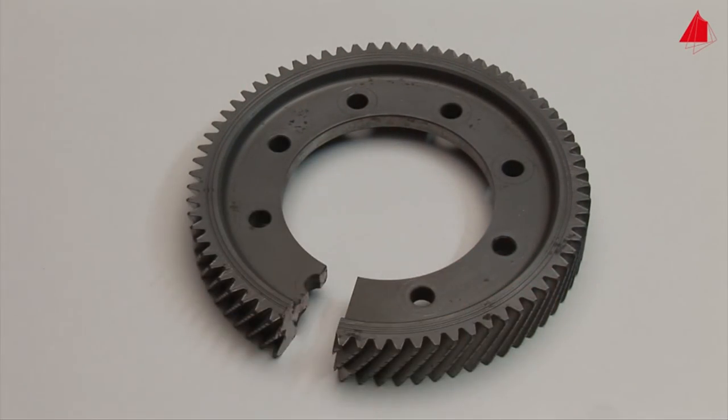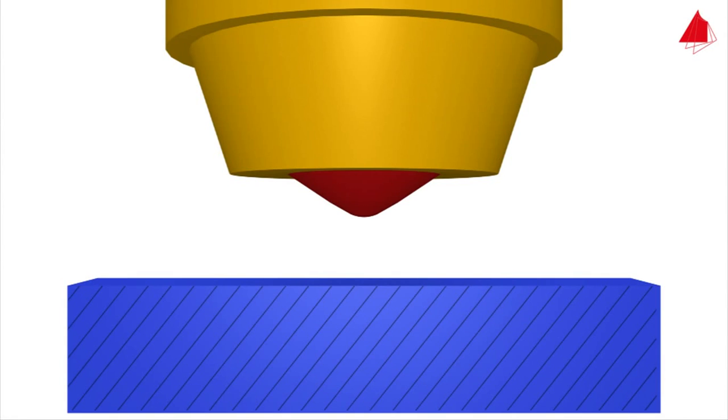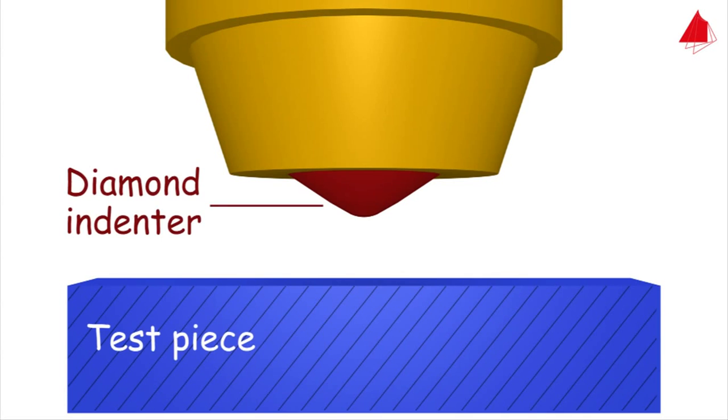The basic idea of this test method is to measure the permanent depth of indentation of a hard indenter under a test force. In the process variant Scale C, a rounded cone made of diamond is used as an indenter.